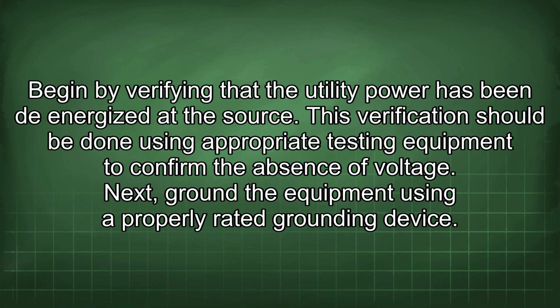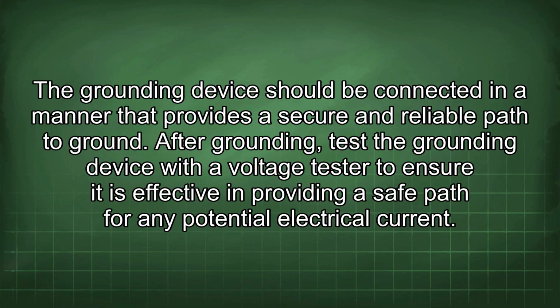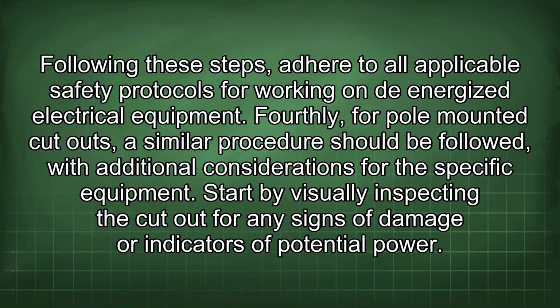grounding. Begin by verifying that the utility power has been de-energized at the source. This verification should be done using appropriate testing equipment to confirm the absence of voltage. Next, ground the equipment using a properly rated grounding device. The grounding device should be connected in a manner that provides a secure and reliable path to ground. After grounding, test the grounding device with a voltage tester to ensure it is effective in providing a safe path for any potential electrical current. Following these steps, adhere to all applicable safety protocols for working on de-energized electrical equipment.